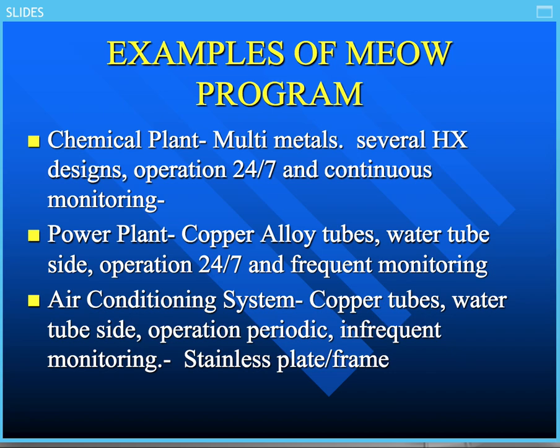In a power plant, in this case, we're looking at another example. It's got copper alloy tubes, water through the tube side always, operates 24/7 and has frequent monitoring. A power plant has a lot of protection built into a system. Sometimes almost all of the heat exchangers are copper alloys, not copper per se, but copper zinc or copper nickel, and that's an excellent minimized corrosion problem for copper. Even though it could use a copper corrosion inhibitor depending upon what the conductivity is, and depending upon what the chloride levels are, etc. From the standpoint of water is always on the tube side, means that you have less fouling, and it's usually got high velocity to the point where it actually gives you really good scouring action through a power plant.